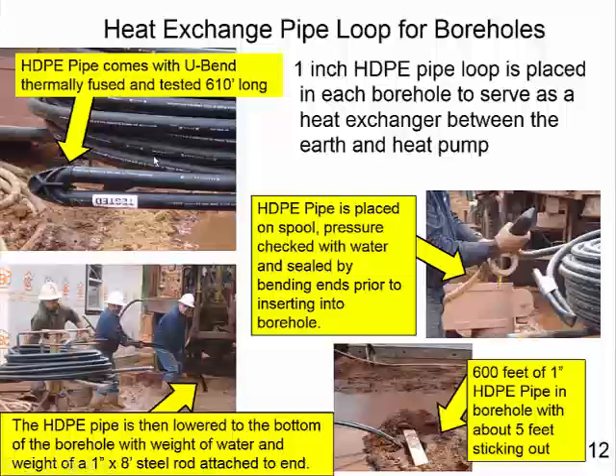The heat exchanger pipe was 1-inch HDPE pipe. It's thermally fused, the U-bend on the end. It's a total of 610 feet long, so it's 305 feet on each leg coming back up to the top. This was filled with water and pressure checked to make sure that the U-bend didn't leak and there were no leaks in the pipes. And once those were filled, the ends were bent over and taped off to keep the water in the pipe.